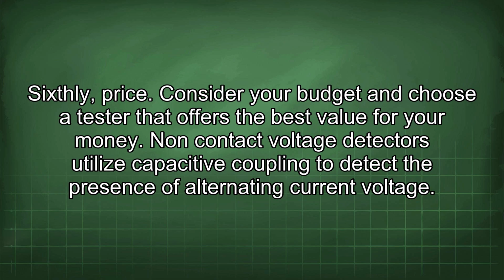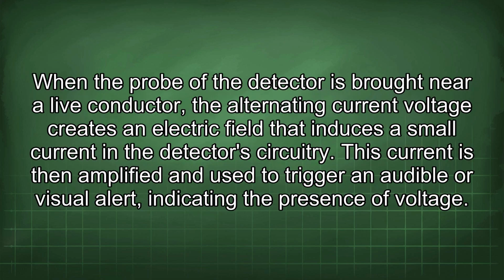Non-contact voltage detectors utilize capacitive coupling to detect the presence of alternating current voltage. When the probe of the detector is brought near a live conductor, the alternating current voltage creates an electric field that induces a small current in the detector's circuitry. This current is then amplified and used to trigger an audible or visual alert indicating the presence of voltage.